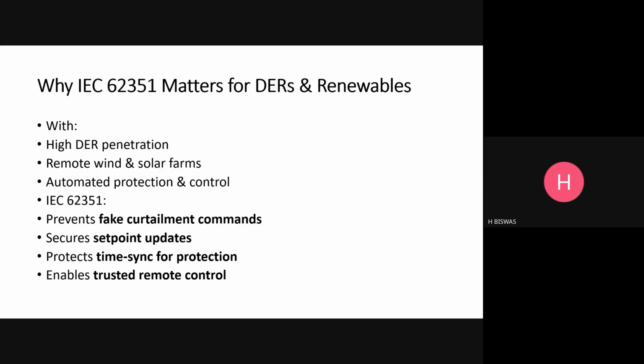So 62351 aims to prevent fake curtailment commands. It secures set point updates, time synchronization for protection, and trusted remote control. Time synchronization is another aspect - it runs through SCADA or PMU, and in addition to the SCADA protocol, it's also contingent on satellite timestamps. This is a very, very delicate thing.